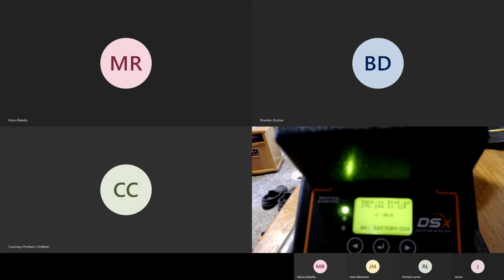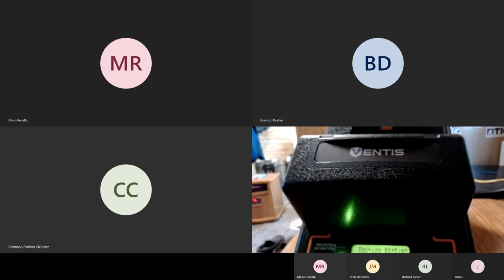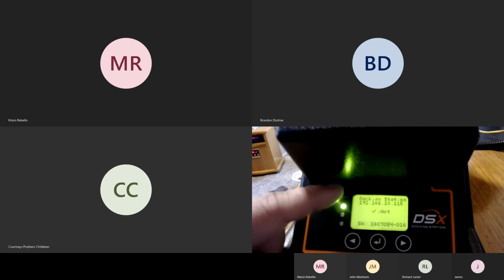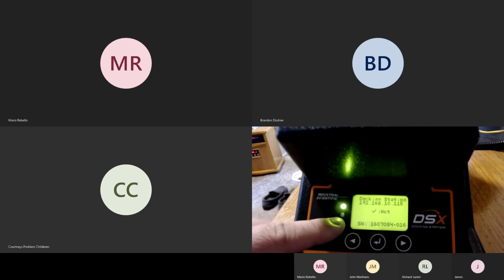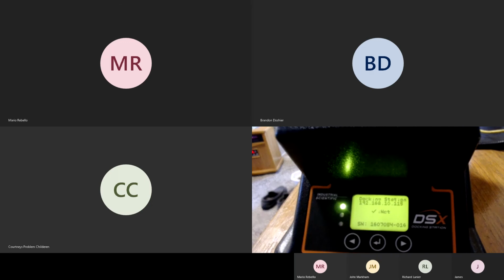Okay. With the docking station, what you're always waiting for is a green light. You've got green, yellow, and red. So it's just like driving a car. Green means go. It means everything's ready to go. In this case, I don't actually have an instrument inside the docking station, so at this point it's not doing anything to an instrument. It's saying, hey, I'm ready and I'm waiting to accept an instrument. Yellow light means slow down. I'm doing something, whether it's running through diagnostics, doing the settings of a new gas bottle, or doing calibration or bump testing. And then finally, down at the bottom is a red light. Red light means, uh-oh, something went wrong.